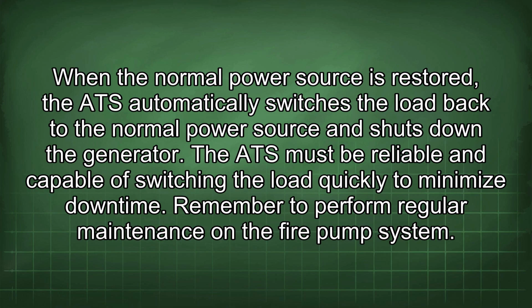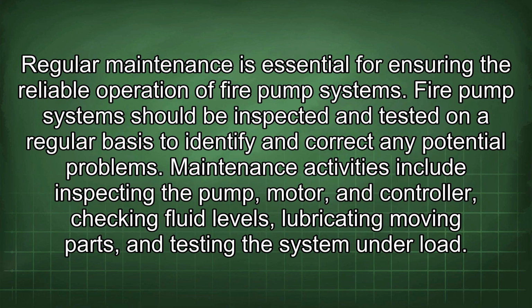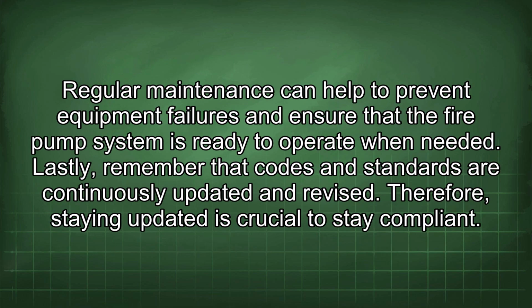Remember to perform regular maintenance on the fire pump system. Regular maintenance is essential for ensuring the reliable operation of fire pump systems. Fire pump systems should be inspected and tested on a regular basis to identify and correct any potential problems. Maintenance activities include inspecting the pump, motor, and controller, checking fluid levels, lubricating moving parts, and testing the system under load.